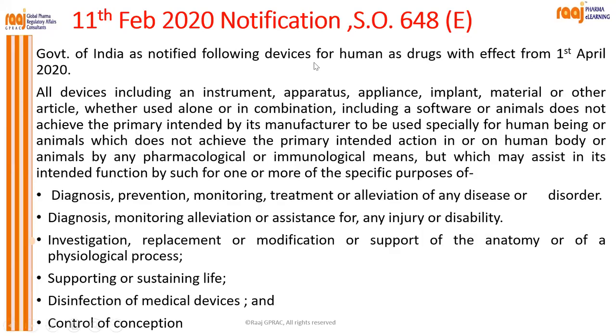As you can see, it was notified that the following devices for humans will be treated as drugs with effect from 1st April 2020. So all kinds of definitions, like Madam explained: the diagnosis, prevention, monitoring, treatment of any disease or disorder, supporting or sustaining life, disinfection of medical devices, control of conception. Every single device which comes under these definitions will be monitored by the CDSCO.